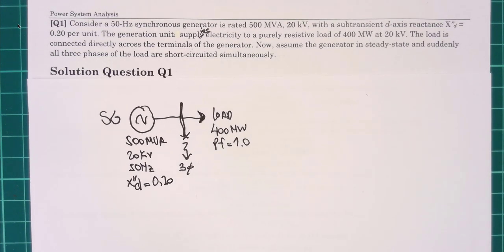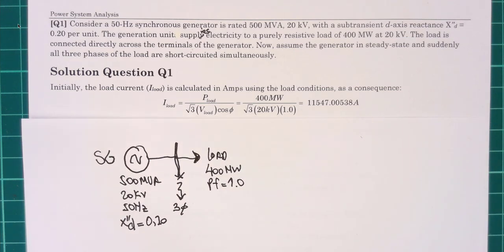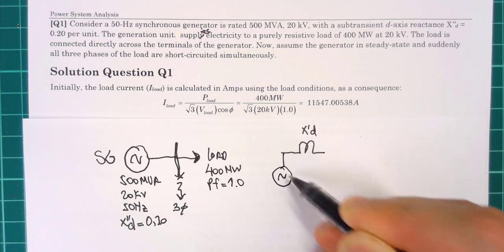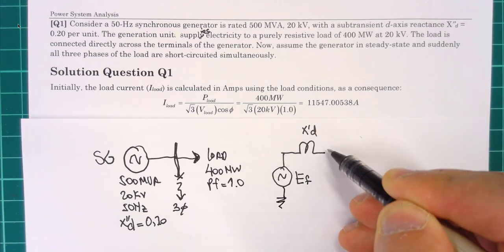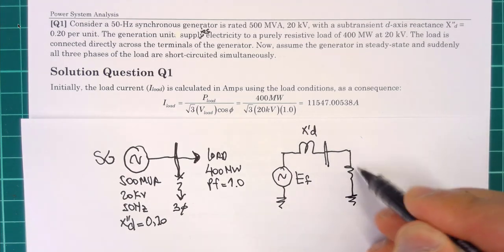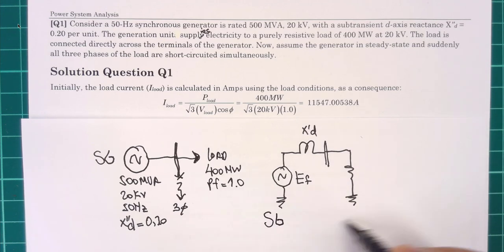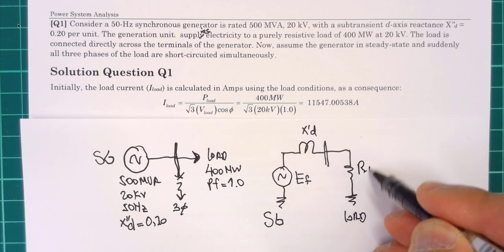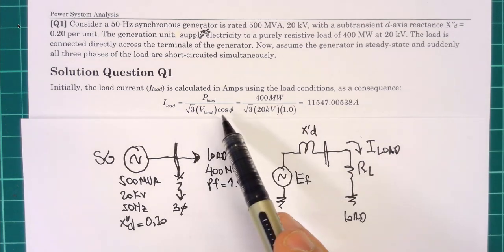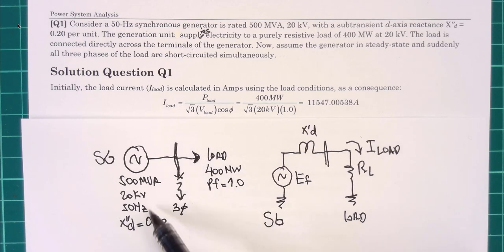We want to find the subtransient short circuit current. We start with the equivalent circuit: we have an internal voltage, a bus bar, and the resistive load. The load current flows when the generator supplies this load at power factor one and line-to-line voltage of 20 kV.